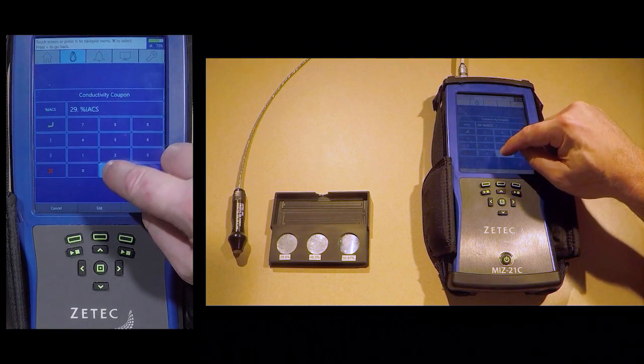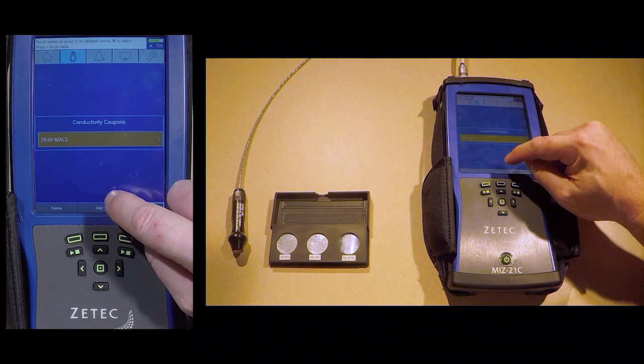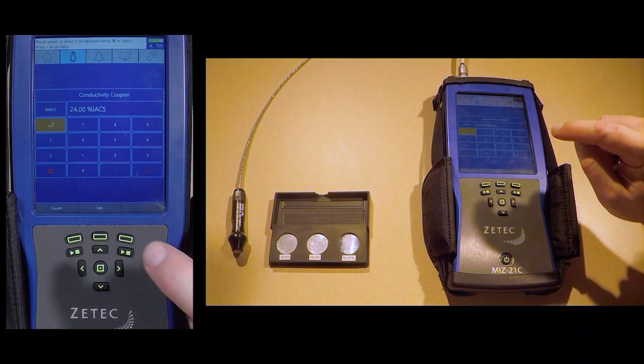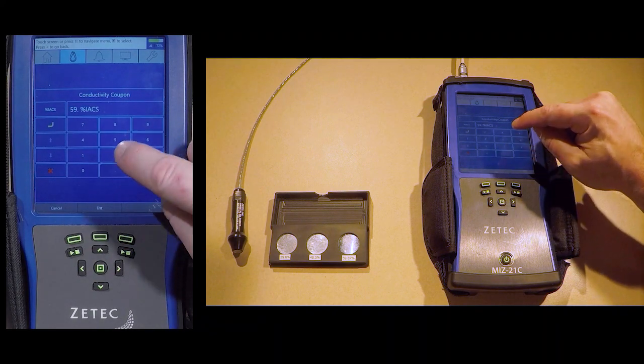For this demonstration, a coupon with the IACS in the high 20s and high 50s will be used for calibration. Our test sample has a conductivity that resides between these two conductivity values.